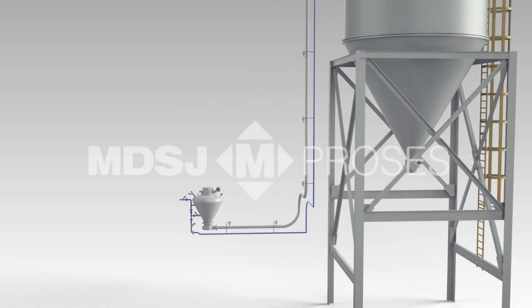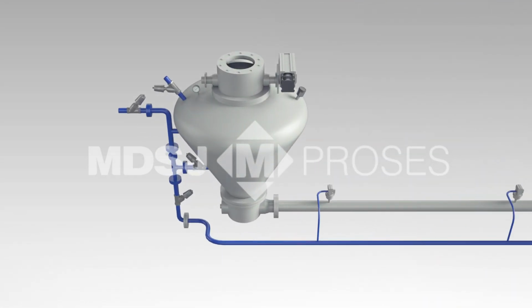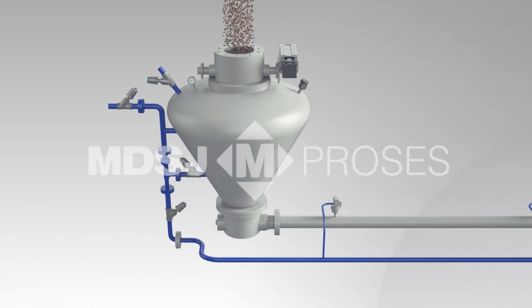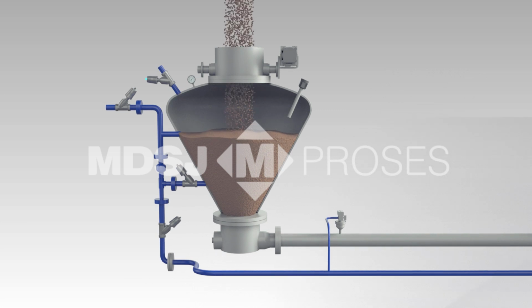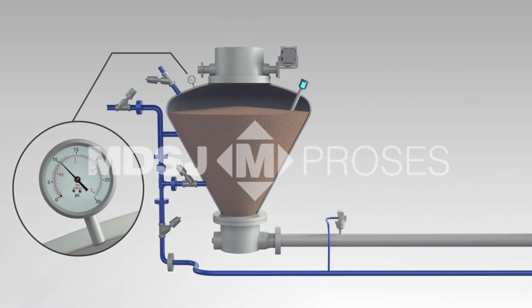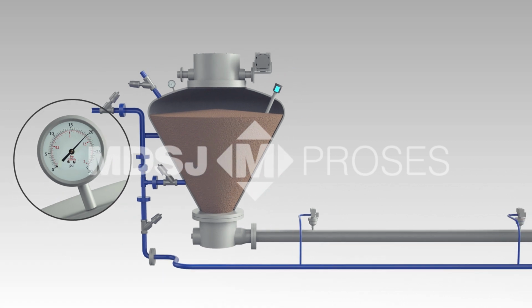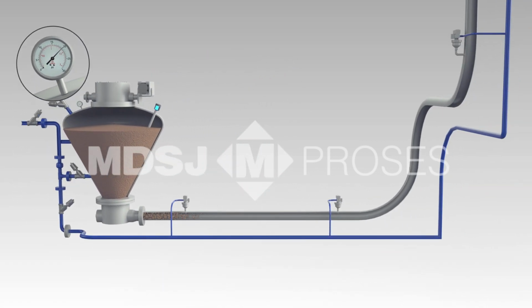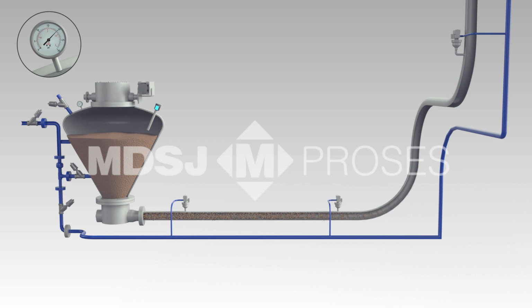Coarse particulates and ashes collected by the cyclones are stored at the silos with the help of densport, also known as dense phase pneumatic conveyor. In the case of an increase of the pressure at the conduit pipe, air is automatically injected from the boosters located on the pipeline, and the transportation pressure gets decreased.